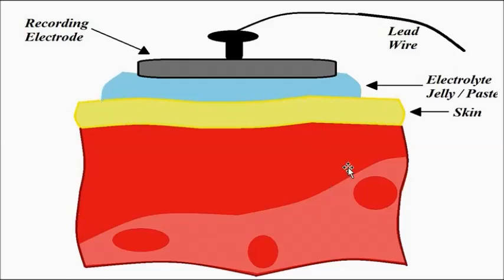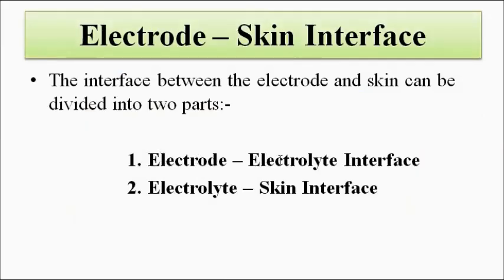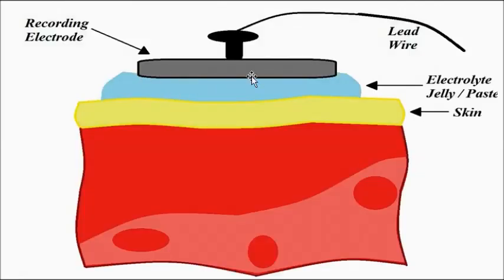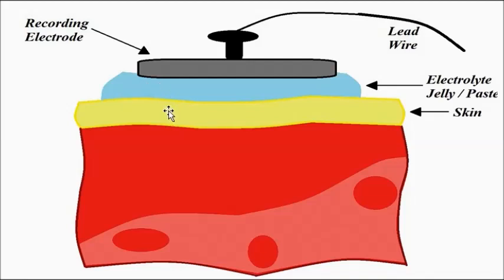This is the pictorial representation of the electrode skin interface. The electrode is shown, and the blue element represents the electrode paste or jelly, which is normally used to achieve firm adhesion. This is the upper layer of the skin. The contact junction between the electrode and the skin, separated by the electrode jelly, is collectively called the electrode skin interface. This can be divided into two parts: the electrode-electrolyte interface, and the electrolyte-skin interface.